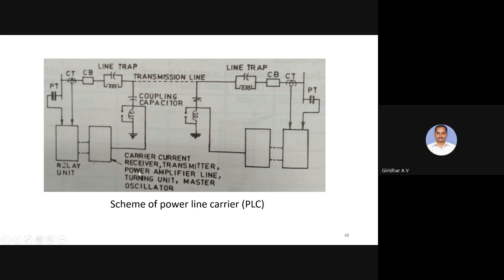So this is the receiver unit, where you can see the high frequency signals arriving from other substations being received by this receiver, and it feeds into the relay unit. The receiving unit consists of an attenuator, band pass filter, and matching transformer. Any signals caused by short circuits, radio interference, and also any mal operation due to noise will be taken care of in this receiver unit. In that way it will be useful.